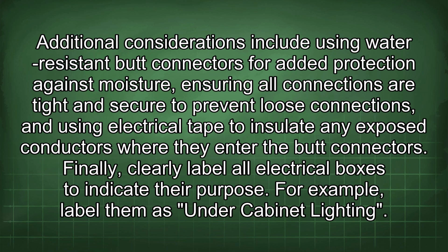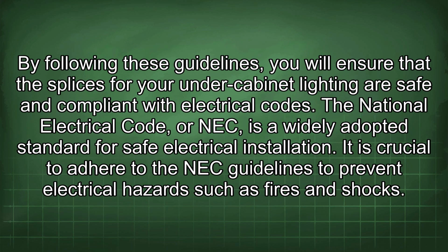Additional considerations include using water-resistant butt connectors for added protection against moisture, ensuring all connections are tight and secure to prevent loose connections, and using electrical tape to insulate any exposed conductors when they enter the butt connectors. Finally, clearly label all electrical boxes to indicate their purpose. For example, label them as under-cabinet lighting. By following these guidelines, you will ensure that the splices for your under-cabinet lighting are safe and compliant with electrical codes.